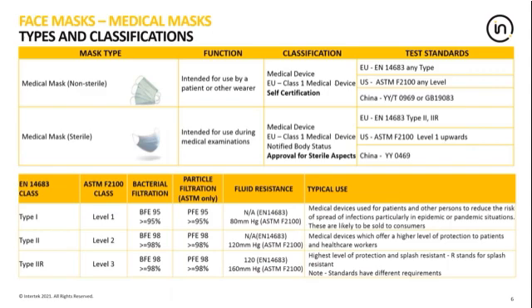Sterile masks should be tested to the same standard, but there are minimum performance level requirements, and for Europe, that should be type 2 or type 2R, and in the US, it should be above level 1. And the lower table illustrates some of the key differences between the performance levels of EN 14683 and ASTM F2100. A major difference is that the US standard has a particulate filtration efficiency requirement, where EN 14683 does not.